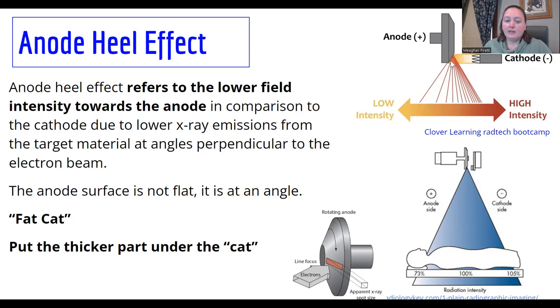Why? Because the anode is not flat. It sits at an angle, and the beam that's coming out on the cathode side can come straight out with nothing in its way. The beam coming out the anode side has to get around the heel or this corner piece here of the anode.